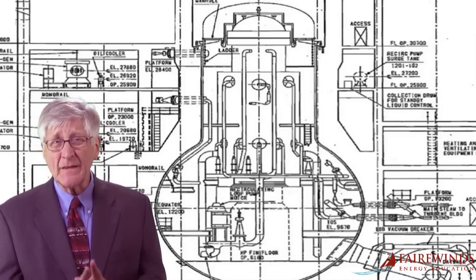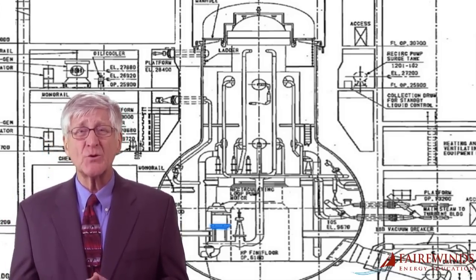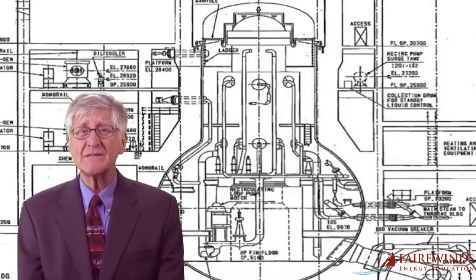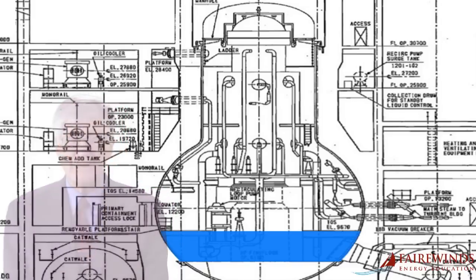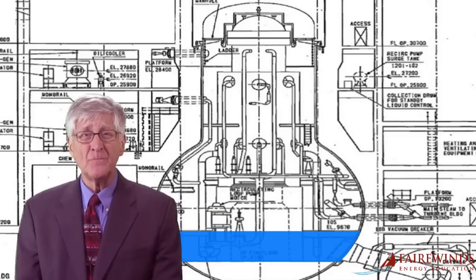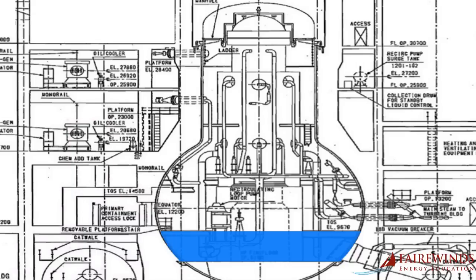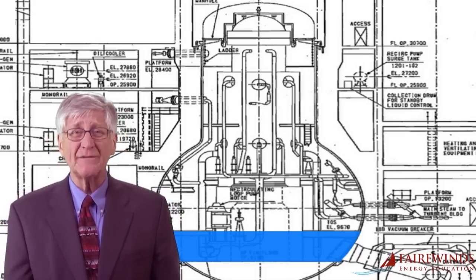Finally, the nuclear core has melted through the thick nuclear reactor and the reactor coolant pumps have also failed. So whatever water reaches the reactor flows out onto the floor and never ever touches the main steam piping, as TEPCO claims. Now, these leaking seals in the containment are what establish the water level inside the containment. The four tons per hour that are pumped in runs right back out. Let's look at a graphic that compares the location of the leak with the water level inside the containment.